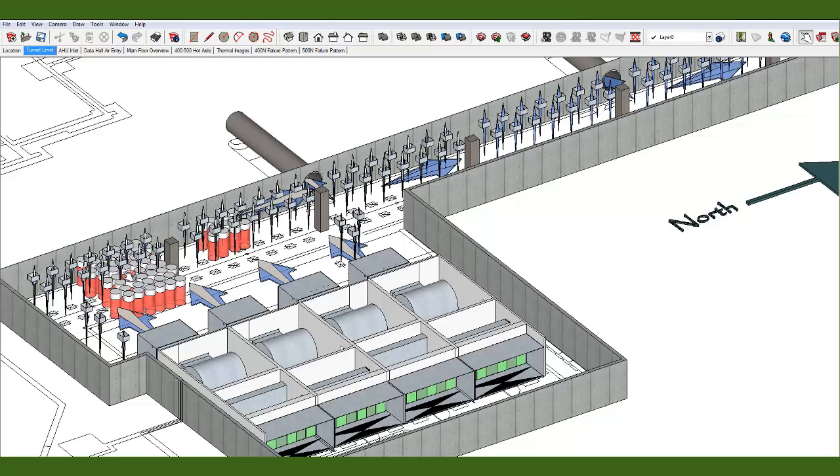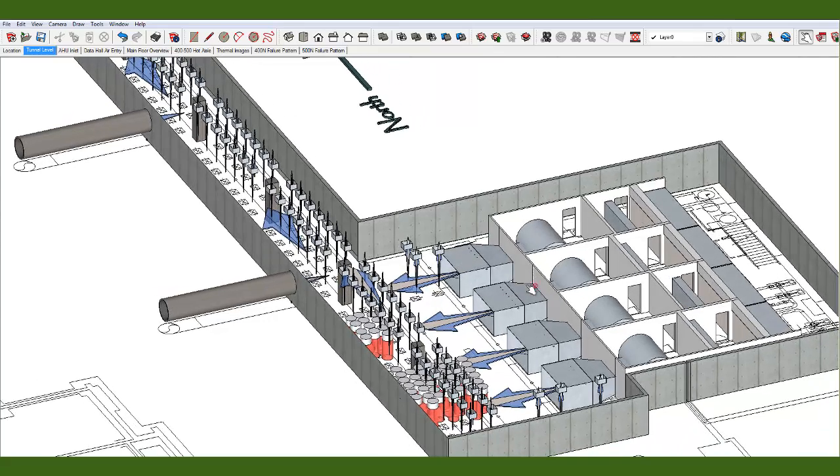They had disassembled that and moved the gas canisters, as you see them down here on the south end, waiting disposal. In the interim, though, they're sitting here in front of the blast of the air handlers, and they were collecting deposits of contamination on the top, which would either be blown into the data hall or enabled to grow, as the case may be.